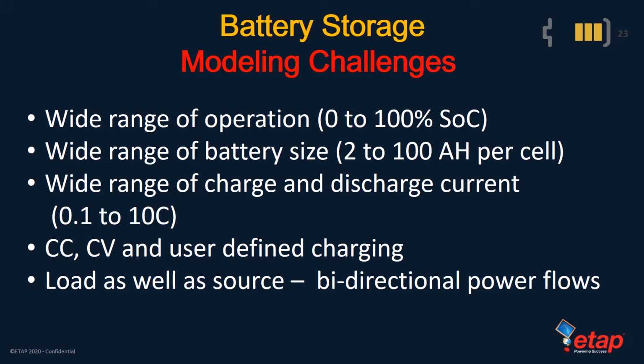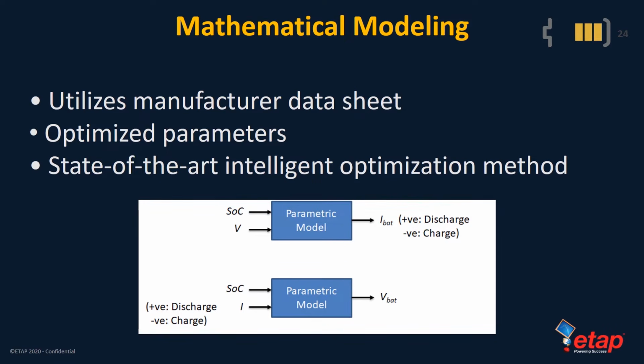There's a wide range of battery sizes going all the way from 2 to 100 amp hours or more. There's a wide range of battery charge and discharge currents that can be used, as we've seen, from 0.1 to 10 C, or current rate. The constant current and constant voltage and user-defined charging profiles can be variable. And the battery itself is a load as well as a source, allowing for bidirectional power flow and requires modeling of the associated power electronics.